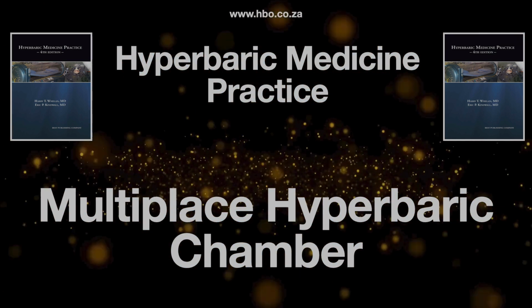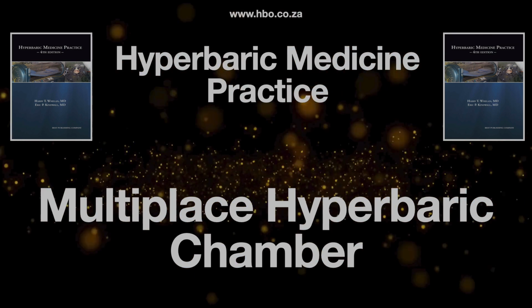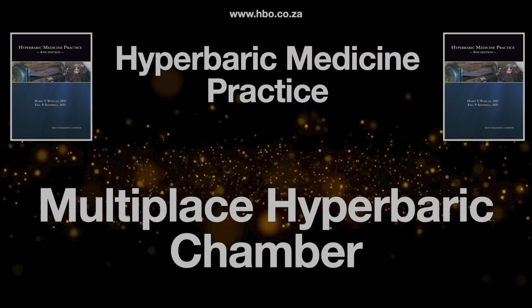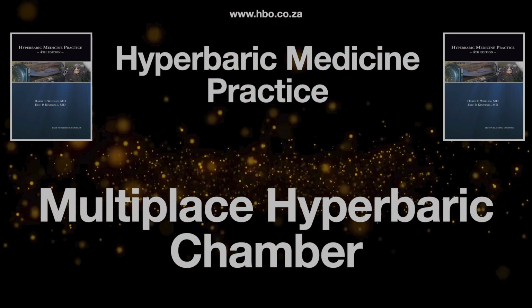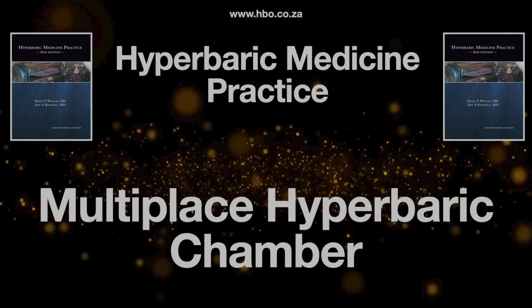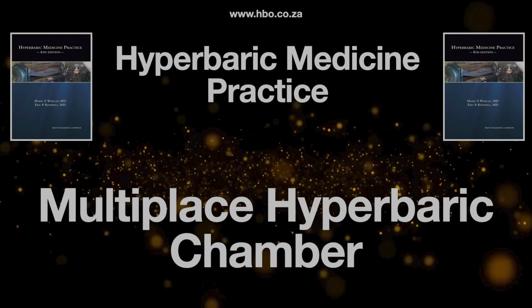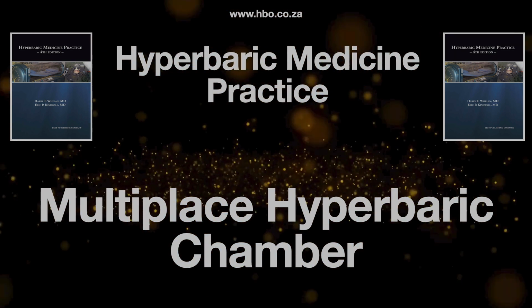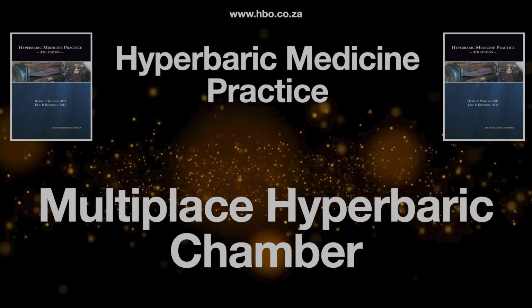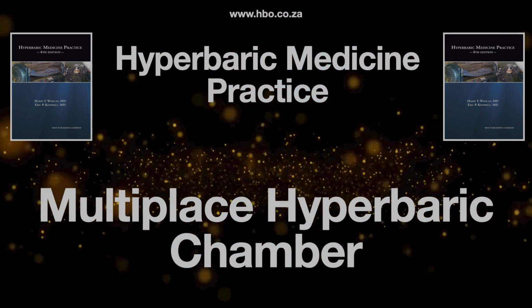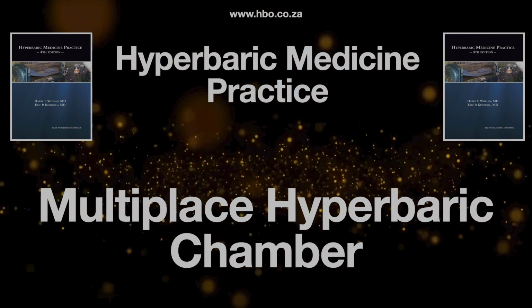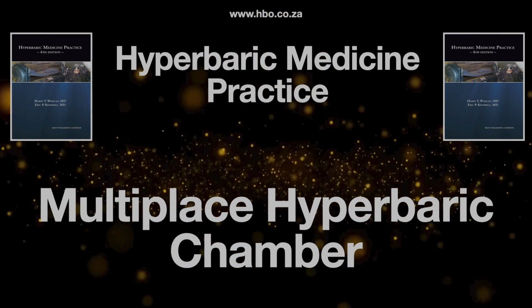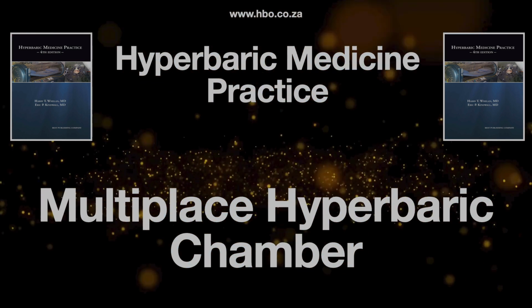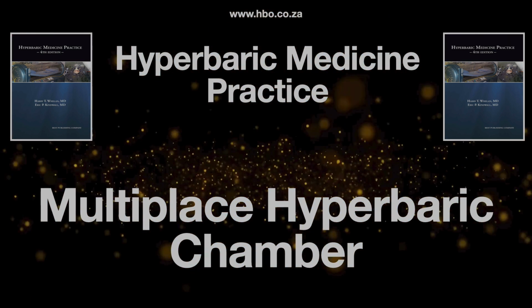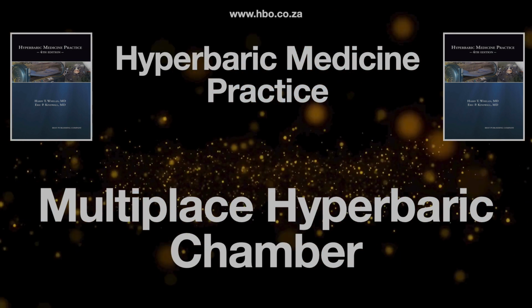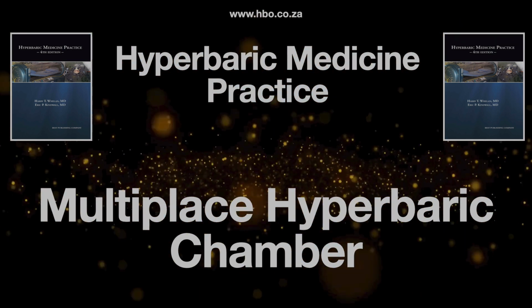Can be for some, yeah. But there's a critical safety point with helmets. If they leak, and they sometimes can, that leakage puts extra oxygen into the chamber environment, increasing the overall O2 concentration, which of course significantly bumps up the fire risk. Oh, I see the problem. Exactly. So because of that potential hazard, European rules often limit how many helmets you can use at the same time inside one chamber. Wow. Fire safety again. It's clearly just woven into every single decision.